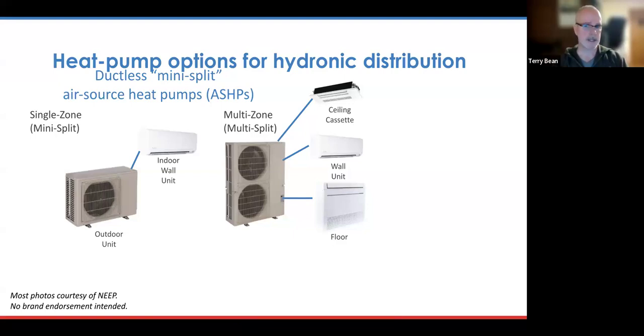There are also ceiling cassettes that you can see pictured on the top. They can be, in some cases, slotted into a ceiling between joists, or in some cases, depending on the configuration, they would require some additional framing. They're a little bit more expensive to install because obviously you have to do that additional work. They're limited in terms of how high the ceiling can be, generally 8 feet. And they're also limited in terms of how far they can be from an exterior wall. But sometimes that's a really nice option if folks are focused on aesthetics. I know they're very popular with architects, for instance. So, and this is another interesting distribution unit.